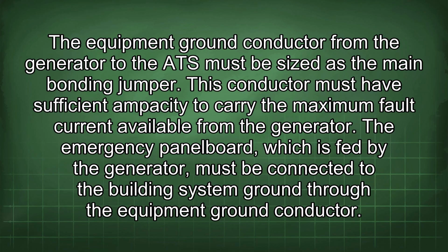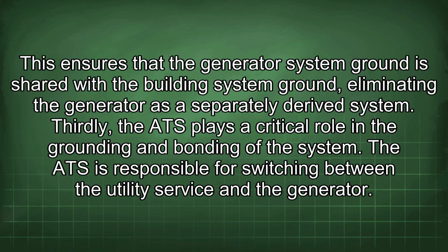The equipment ground conductor from the generator to the ATS must be sized as the main bonding jumper. This conductor must have sufficient ampacity to carry the maximum fault current available from the generator. The emergency panel board, which is fed by the generator, must be connected to the building system ground through the equipment ground conductor. This ensures that the generator system ground is shared with the building system ground, eliminating the generator as a separately derived system.